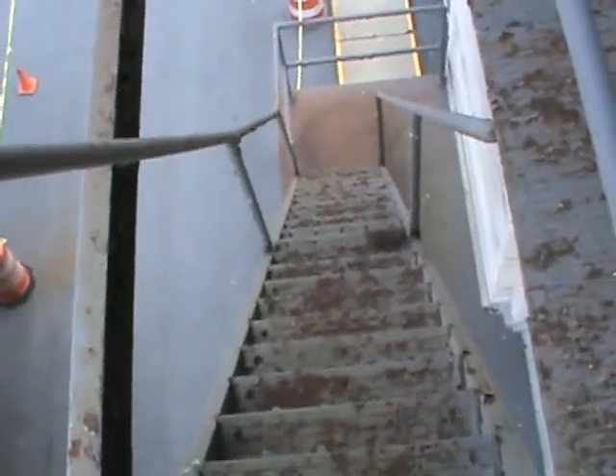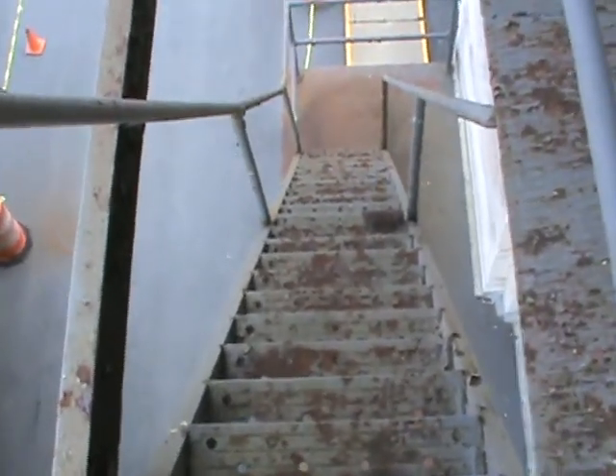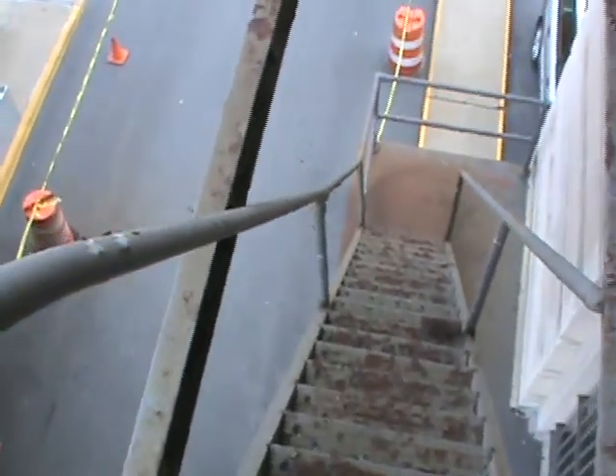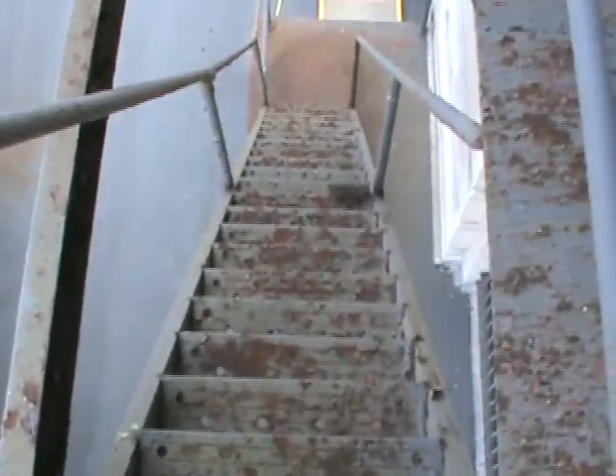Or you can go for the refurb at this time to avoid the load test, not just now, but the IFC code now requires, Chapter 11, every 5 years you have to load test this fire escape under the IFC. But if you refurbish it at this time, you can put off the load testing for the next 15 to 25 years because you'll be providing them with other evidence of strength under a structural engineer's certification. So I'm going to stop here, and I'm going to continue once I get beyond these treads. I need both hands.